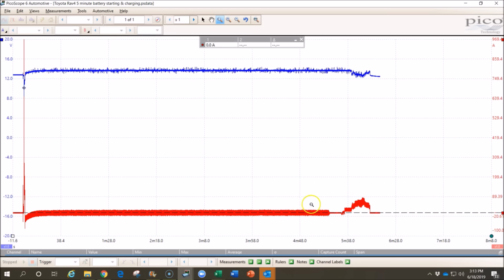But if we come out here at about 5 minutes and pick a spot, we want to find out. It still is negative. You'll see it's still averaging below this 0 line, which is expected because there will always be some current flowing into the battery as long as the voltage at the generator is higher than the battery voltage. But because of all this noise and hash, I can't determine what the actual number is, so I'm going to bring out a set of rulers.